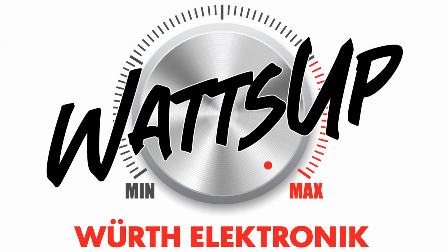And the third one, which you see in yellow color or orange color, is a nanocrystalline material, which does not belong to the class of ferrites, which is a specific material which usually has a very high permeability. This can already be seen when we look at the central part of this diagram, where the transition from the negative field level to the positive field level is quite steep. And this transition or the slope of the transition indicates and is proportional to the permeability of the material. So when it's very steep, the permeability is high.